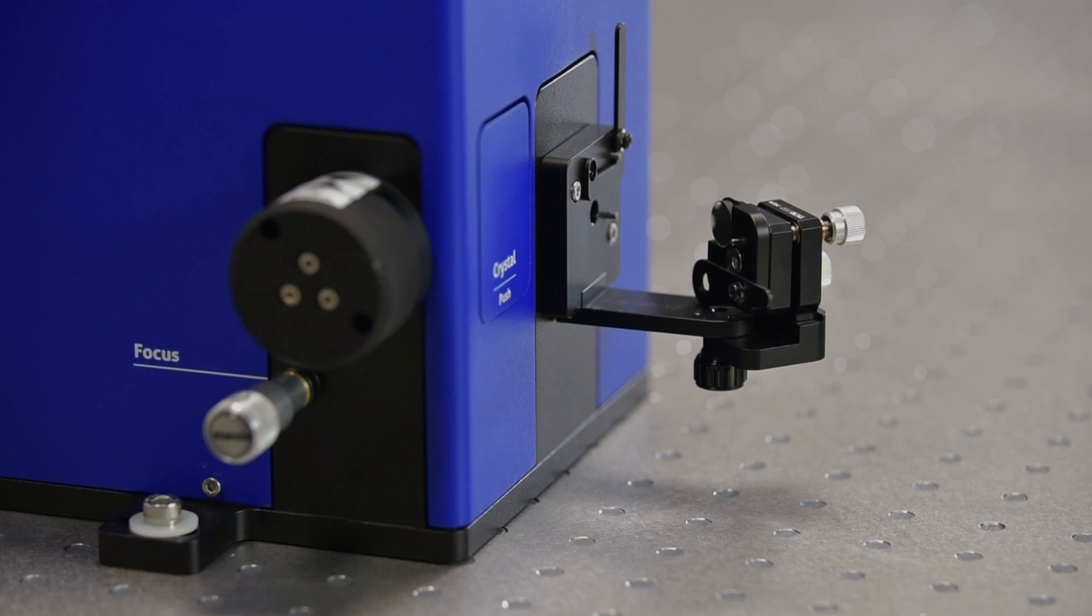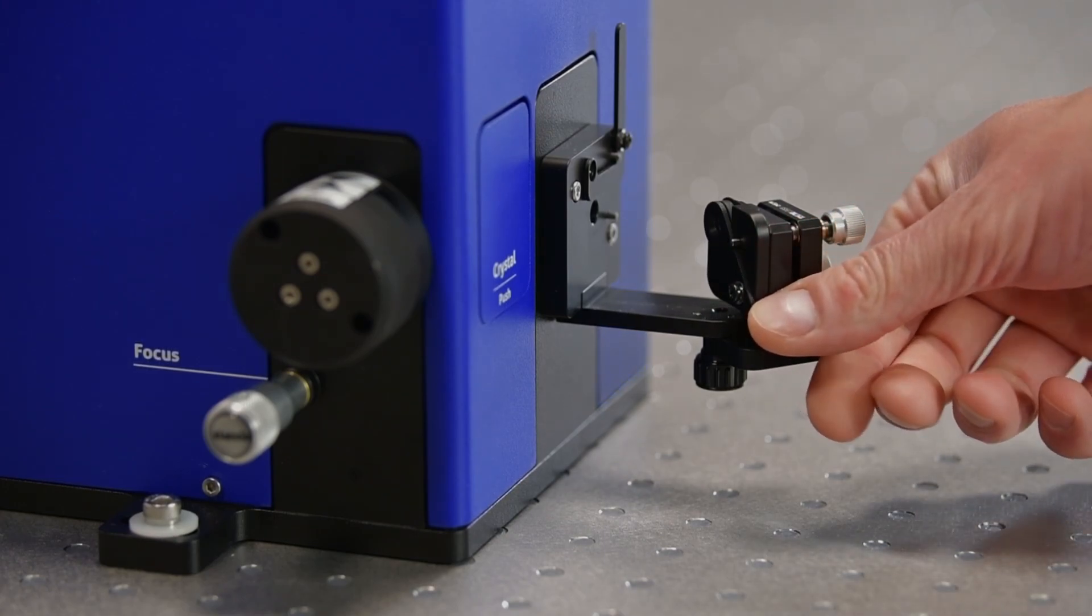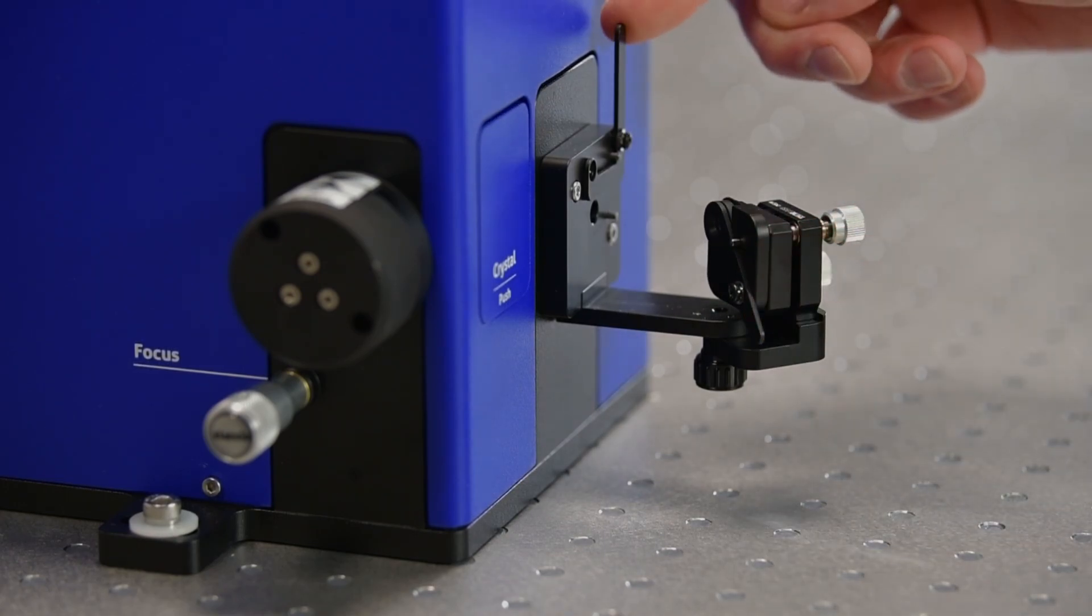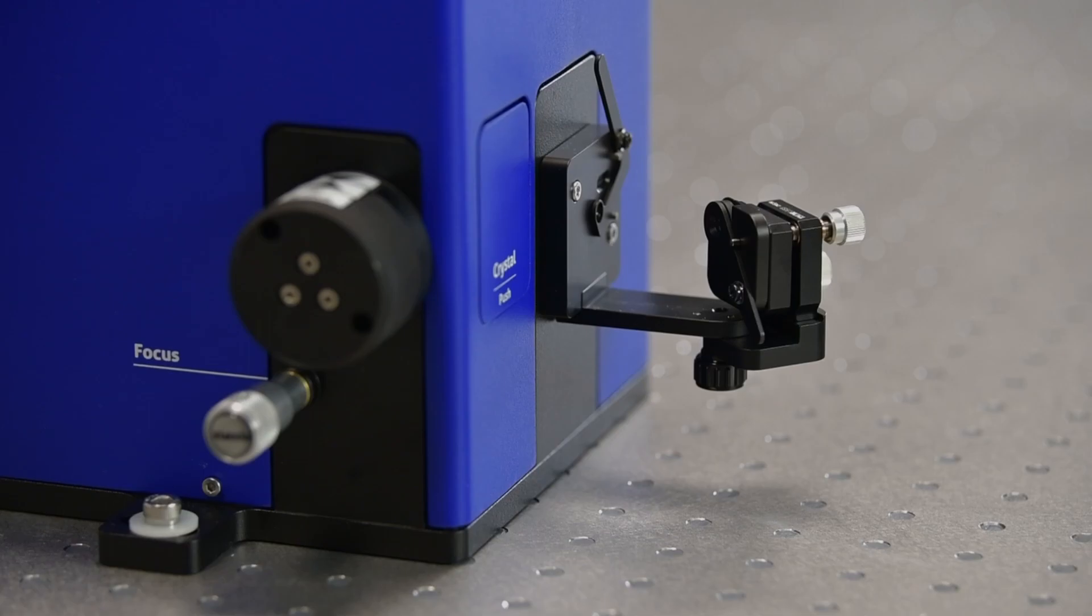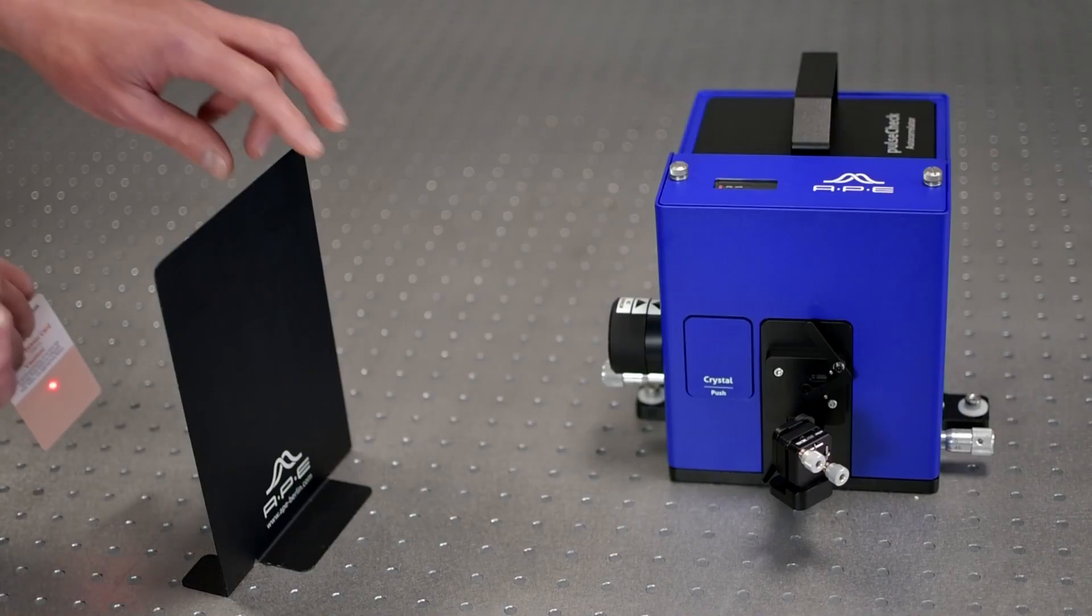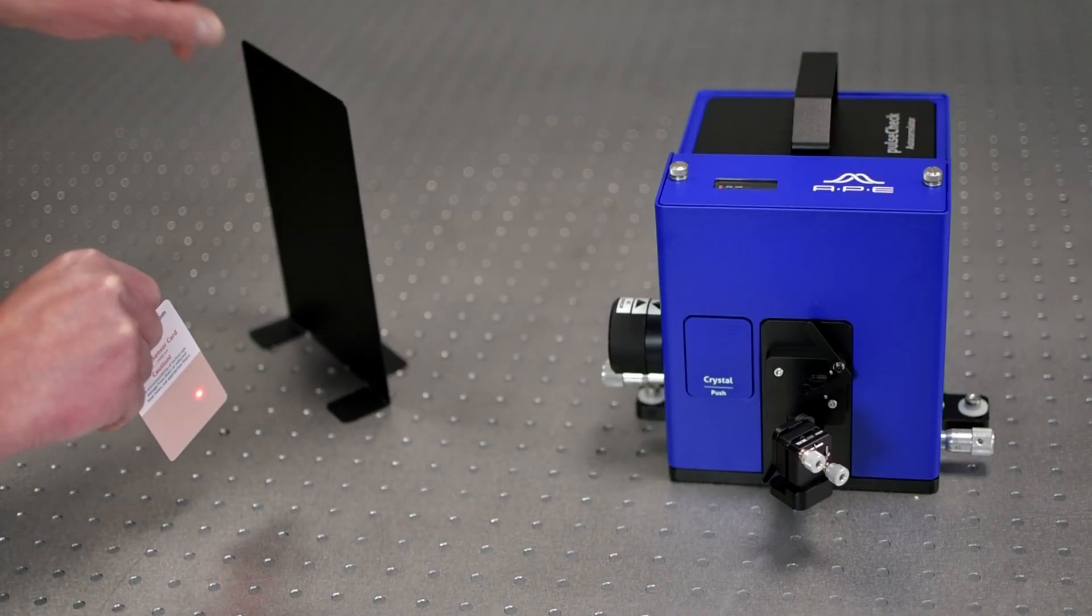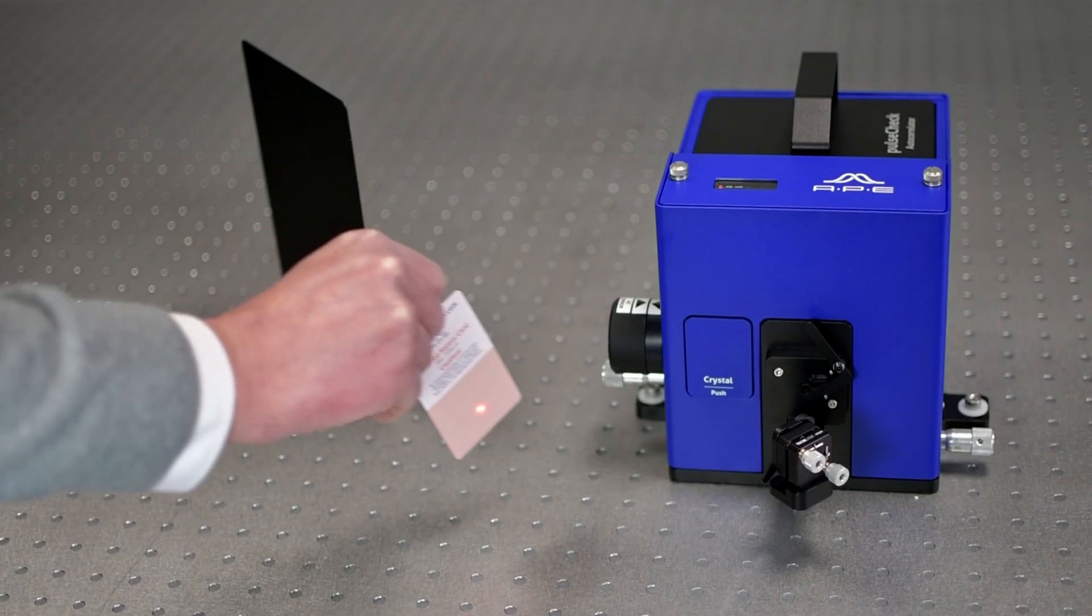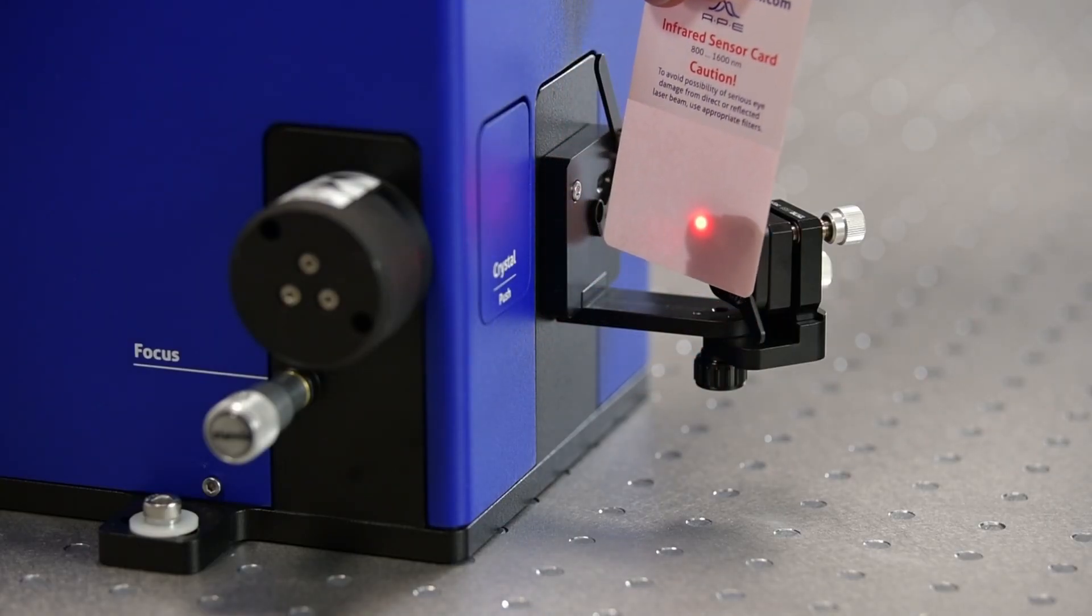Flip down the two input apertures to center the beam more easily later. Then, remove the beam block and direct the beam to the first input mirror. If the laser beam is not visible, use appropriate IR cards or an IR beam viewer.